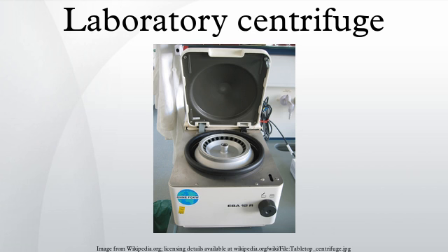Before starting a centrifuge, an accurate check of the rotor and lid locking mechanisms is mandatory. Centrifuge rotors should never be touched while moving, because a spinning rotor can cause serious injury. Modern centrifuges generally have features that prevent accidental contact with a moving rotor as the main lid is locked during the run. Centrifuge rotors have tremendous kinetic energy during high-speed rotation.